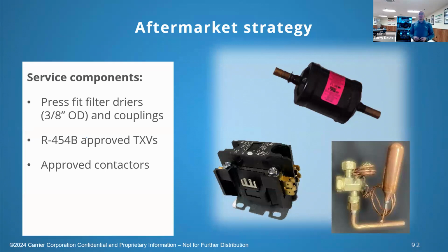Replacement components, again: make sure when you're replacing a dryer, expansion valve, especially the contactor, you don't just grab one of the old contactors off your truck and throw it on there. Make sure it is a contactor that is rated for use with 454B refrigerant, that it has those contact points sealed. Okay.